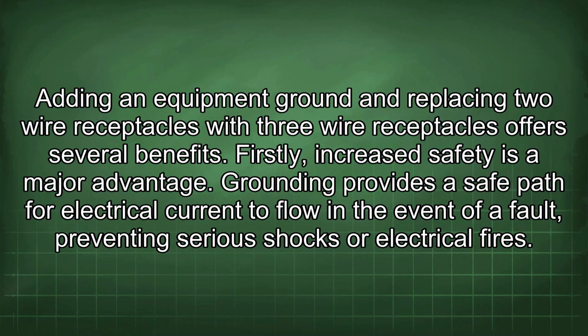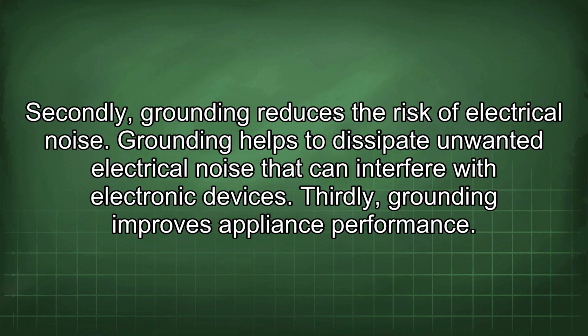Adding an equipment ground and replacing 2-wire receptacles with 3-wire receptacles offers several benefits. Firstly, increased safety is a major advantage. Grounding provides a safe path for electrical current to flow in the event of a fault, preventing serious shocks or electrical fires. Secondly, grounding reduces the risk of electrical noise.